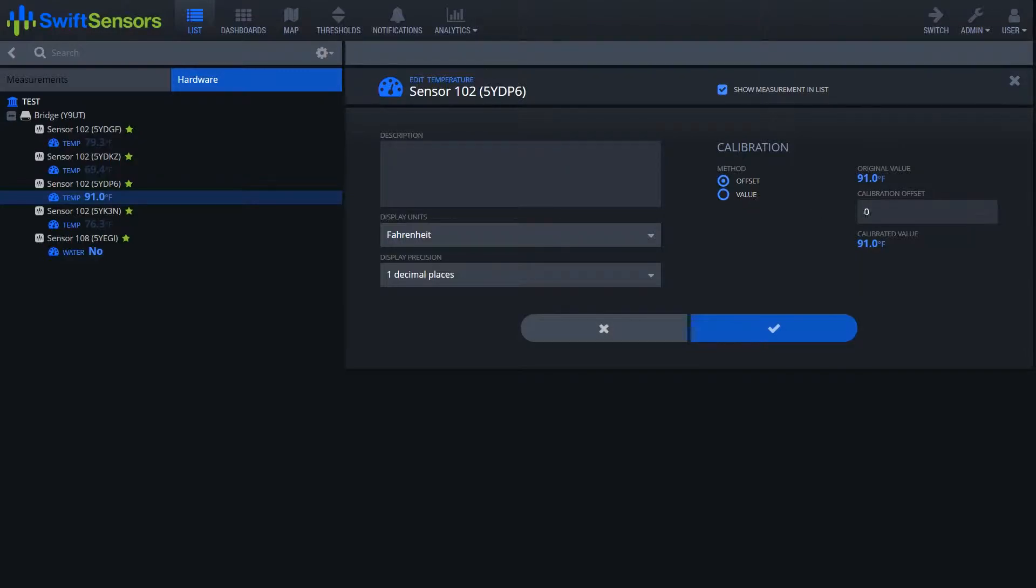Basically with an offset you go over here on the right hand side and enter in either a negative or positive number. Once we enter in say positive five, you'll notice the calibrated value goes up five degrees. If we enter in negative five, the calibrated value goes down five degrees.